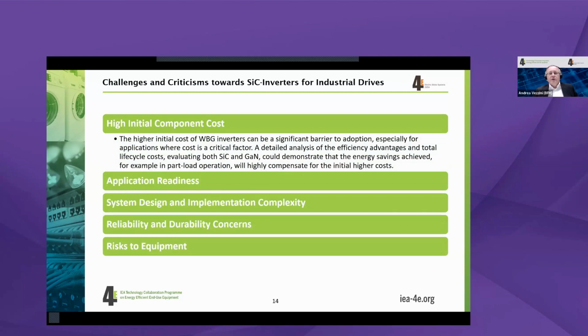If we go now point by point, as I said, the high initial cost is really a significant barrier for adoption when the application cost is a critical factor. And in most industrial applications, the investment at the beginning is regarded as critical. So it's very important to have a look at the detailed analysis of the costs, and look at whether, over the life cycle of the inverter, the efficiency advantage will also bring a cost advantage. One of the outcomes of this is that we have to demonstrate that the energy savings you can achieve actually compensate for the higher initial cost.